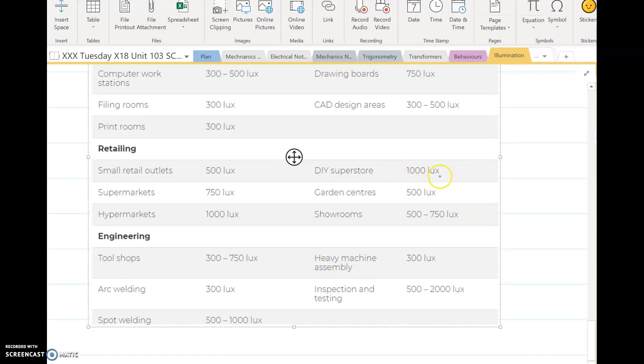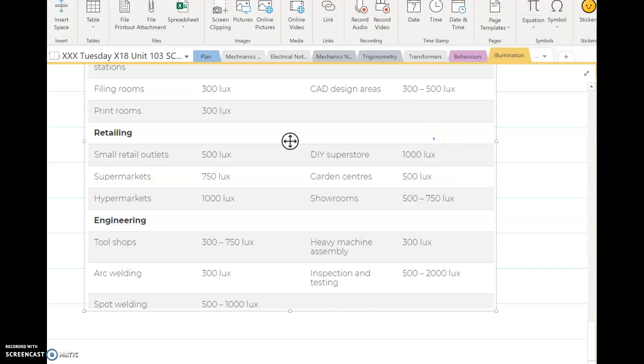Retailing though is very high, 1,000 lux for your superstores, hypermarkets, supermarkets. That's why when you walk into these places they're really bright, and the high bay lighting produces quite a lot of lumens. Your engineering workshops depends on the activity. If you are welding, 300 lux, right up to 2,000 lux. This depends very much on inspection and testing, so if you are building engines or assembling electronic circuits, you're going to need a very high level of lux for the detail. So this is a good guide to give you an idea on where to start and how many lights you would need.